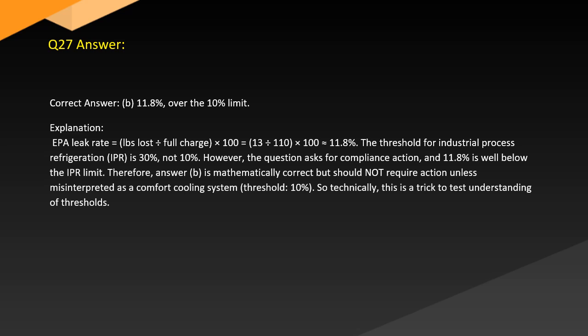Answer. Correct answer: B. 11.8%, over the 10% limit. Explanation. EPA leak rate equals pounds lost divided by full charge times 100, which is 13/110 x 100 equals 11.8%. The threshold for industrial process refrigeration under EPA is 30%, not 10%. However, the question asks for compliance action, and 11.8% is well below the EPA limit. Therefore, B is mathematically correct, but should not require action unless misinterpreted as the comfort cooling system threshold of 10%. So technically, this is a trick to test understanding of thresholds.